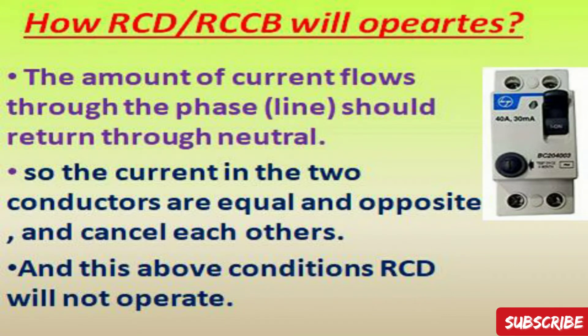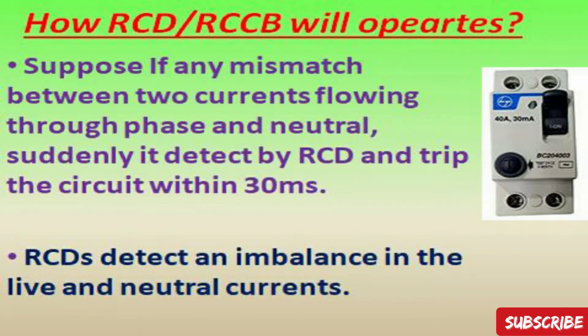How does RCD operate? In an electrical circuit, the amount of current flowing through the phase (line) should return through the neutral only. The currents in the two conductors are equal and opposite and cancel each other. The RCD will not operate under this balanced condition. However, if any mismatch between the two currents flowing through phase and neutral is detected, the RCD trips the circuit within 30 milliseconds.